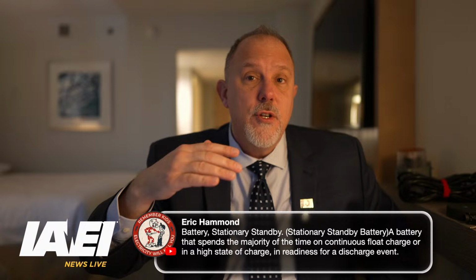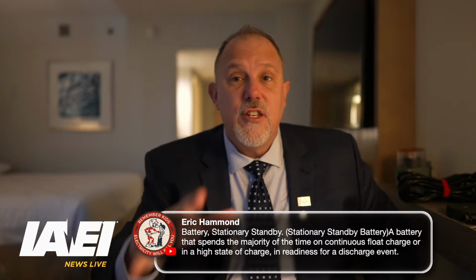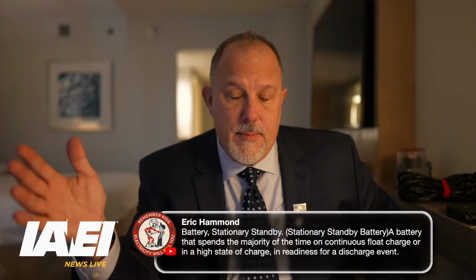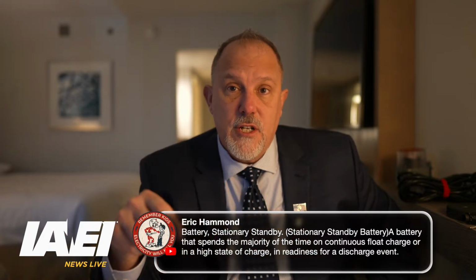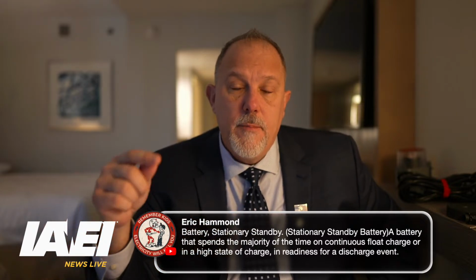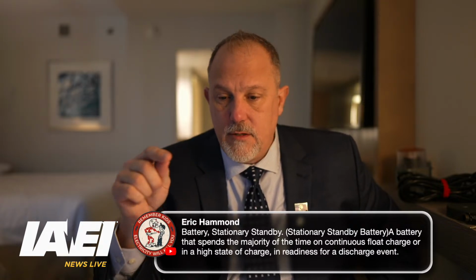But we had two different scenarios, and we had to make sure the battery load profiles were such that I did not drain the batteries but achieved my goal, which was to safely shut down the plant. Those batteries were there not for ongoing use, but only for that one emergency situation.